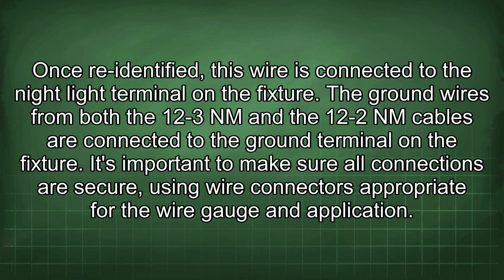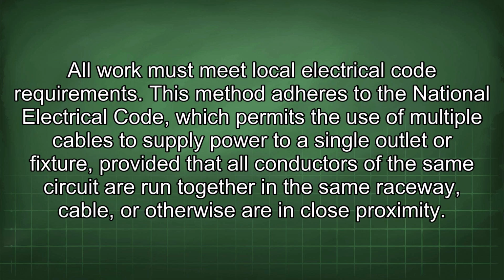The ground wires from both the 12-3 NM and the 12-2 NM cables are connected to the ground terminal on the fixture. It's important to make sure all connections are secure, using wire connectors appropriate for the wire gauge and application. All work must meet local electrical code requirements.